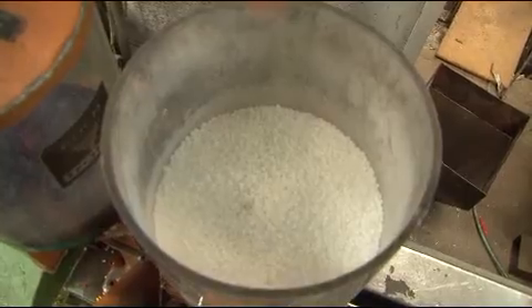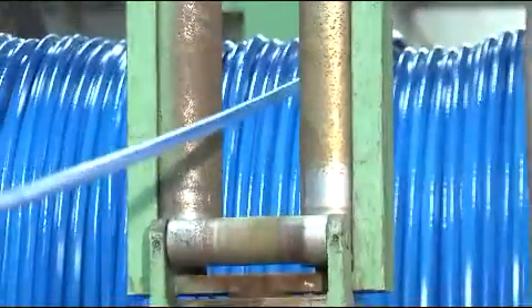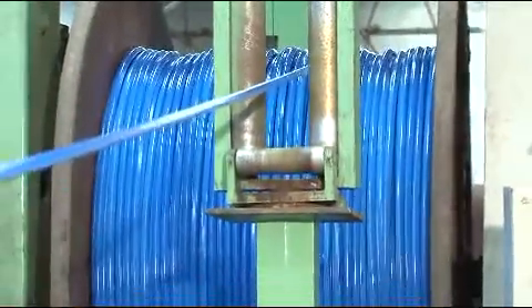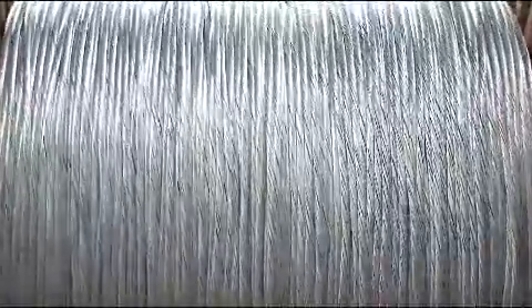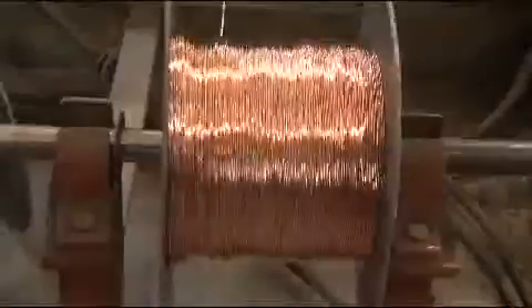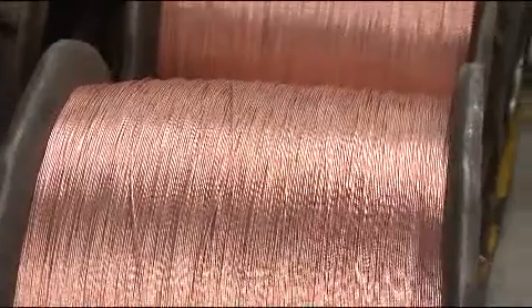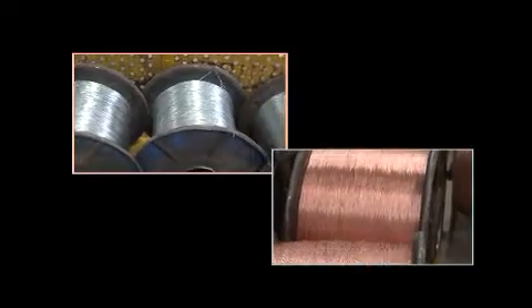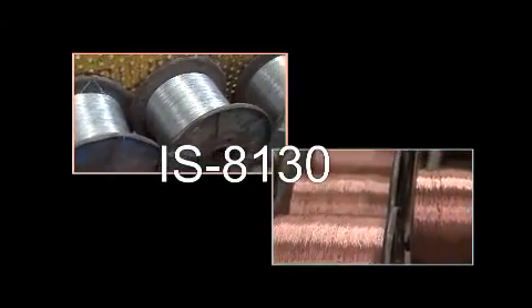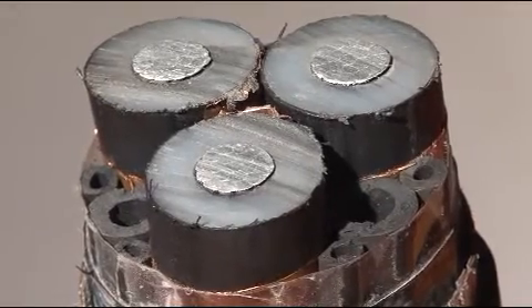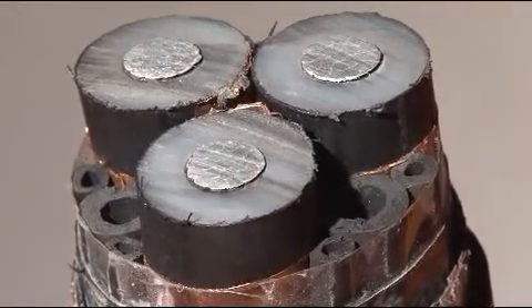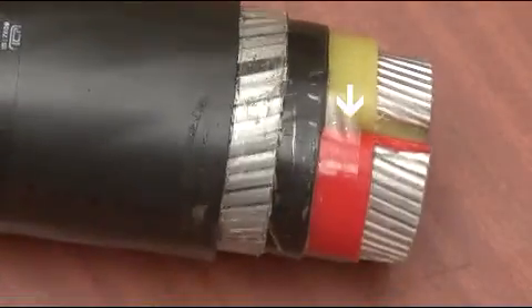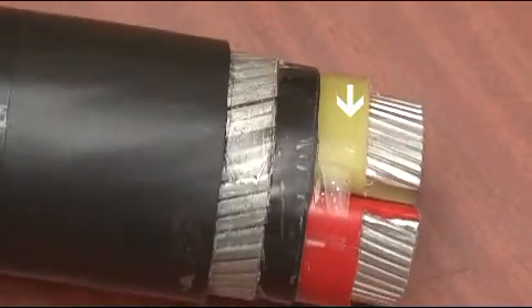Cross-linked polyethylene as insulation material has certain advantages like low dielectric loss, high power rating, resistance to moisture, chemicals and corrosive gases. It also has the capacity to withstand localized temperatures. The power cables are made from pure aluminium and the control cables are made from annealed high conductivity copper. All conductors conform to the IS 8130 standard.